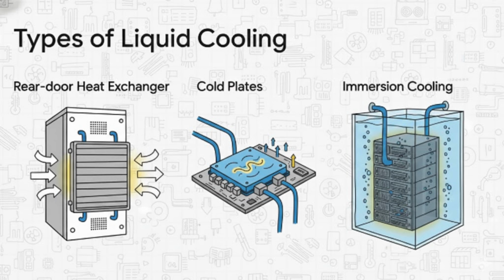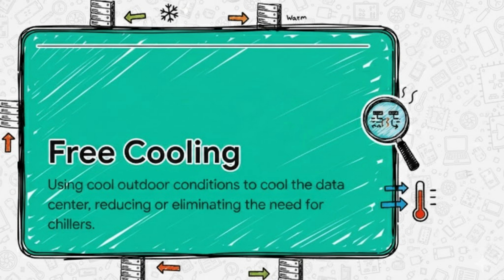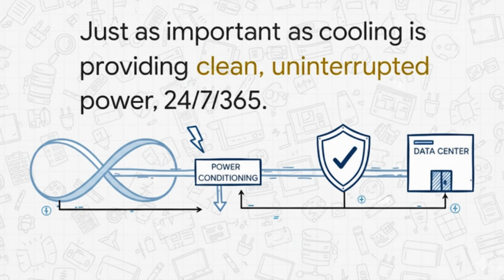Now, regardless of the cooling method, one of the biggest opportunities for savings is something called free cooling. It's a simple idea: instead of running your massive energy-guzzling chillers, you just use the cool outside air or water to do the work. And this connects right back to running the data center warmer. The warmer your data center can operate, the more hours per year the outside temperature is cool enough to provide you with free cooling. So cooling is half the battle. The other half is power.